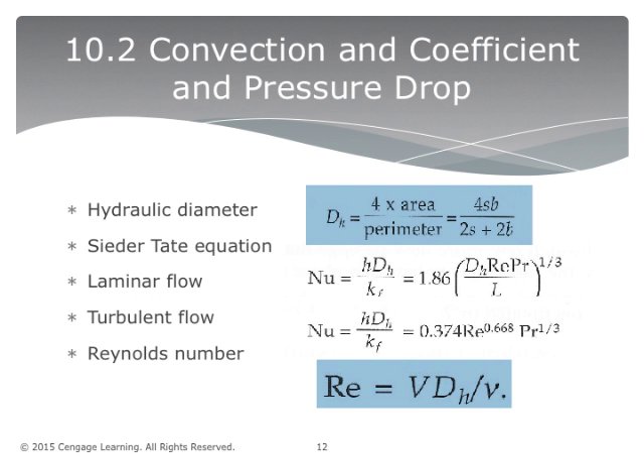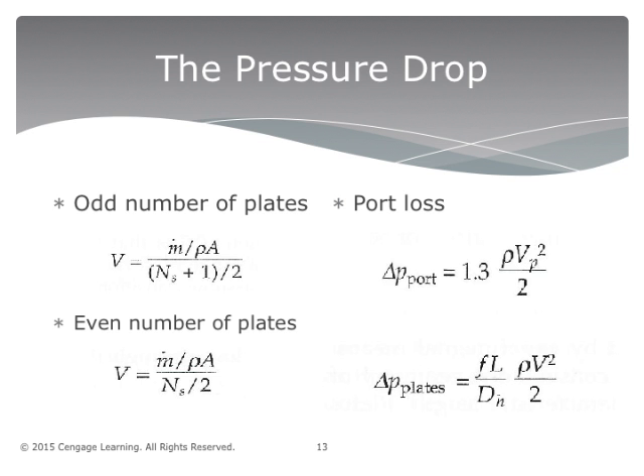Convection coefficient and pressure drop. The hydraulic diameter for a rectangular flow section is dH equal to 4SB divided by 2S plus 2B, where S is the distance between the plates and B is the width gasket to gasket. The port loss is calculated as a loss coefficient multiplied by the kinetic energy of the flow in the port, inlet or outlet itself. Delta P port is equal to 1.3 times rho Vp squared divided by 2, where Vp is the velocity in the port. The total measured loss associated with the flow streamed through the exchanger is then the sum of delta P plates and delta P port.